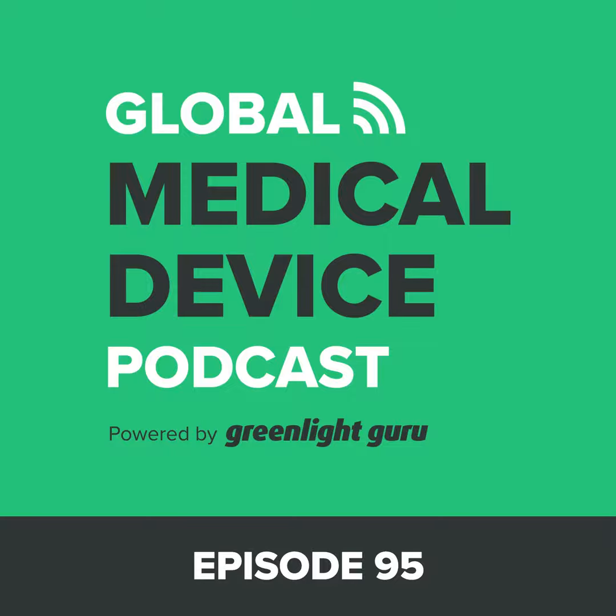If it is something that has significant risk, then absolutely, it's without a doubt. If it is something with significant risk and you have several critical tasks that are going to result in harm, then absolutely you need it. And that needs to be a separate dossier filing, following the FDA human factors guidance, and they're very clear on it.